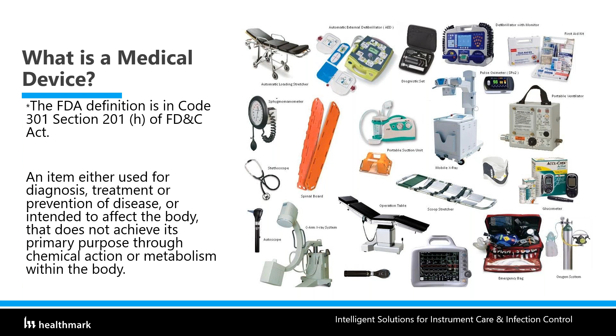Sometimes, as a lonely biomed in a smaller hospital, if something doesn't fall under maintenance, I usually get called in to look at it. But if you want to know whether something that comes into the hospital is a medical device, or whether it's cleared by the FDA, you go into the database and look at the devices either by classification, class 1, 2, 3, or HDE, or by model number. It gives you a general idea, first of all, whether this device is FDA regulated and in the database.